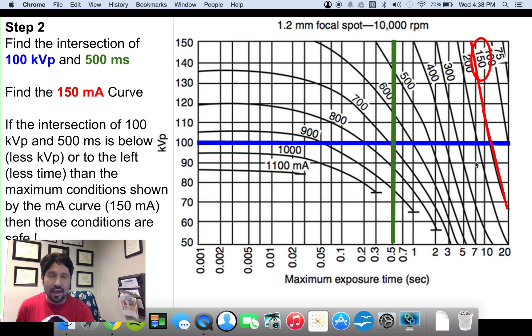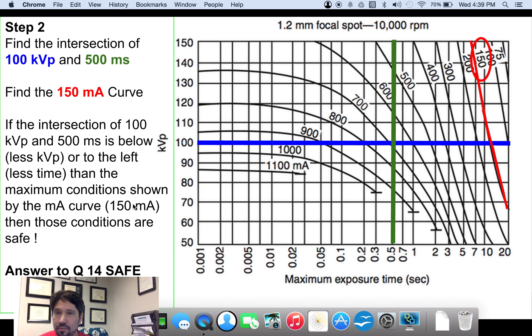So in this problem, we would say that it's safe because the intersection of 100 kVp and half a second is far to the left and far below this curve. So we're to the left and below this curve, which is our maximum kVps and time that we can do at that exposure at that current rate.